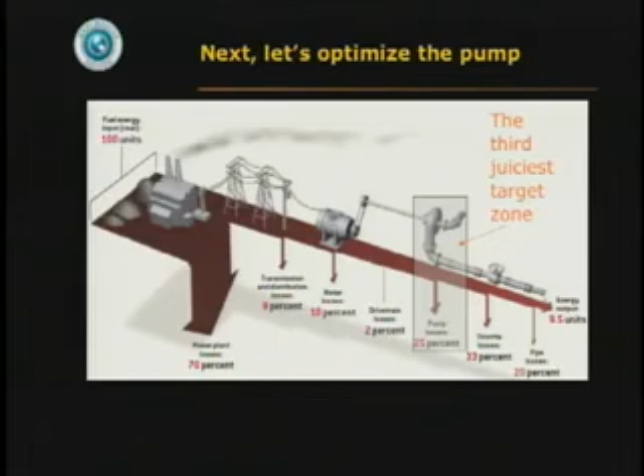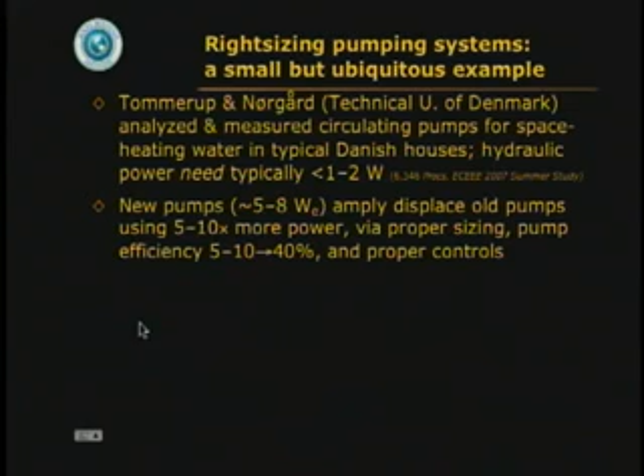Yeah. Now, once we've gotten rid of the flow and friction we don't need, let's optimize the pump, going back upstream a little further. A couple of friends of mine at the Technical University of Denmark looked at a tiny little use, circulating pumps for hot water to heat your house in Denmark. It turns out that the circulation actually requires 1 or 2 watts, often less than 1 watt. But new pumps use 5 to 10 times the power they should, and they're very inefficient, and they're not properly controlled. But in Europe, they've developed pumps of that small size that go from 5 or 10% efficient up to 40, they control them properly, and now new European building standards make that worth doing.